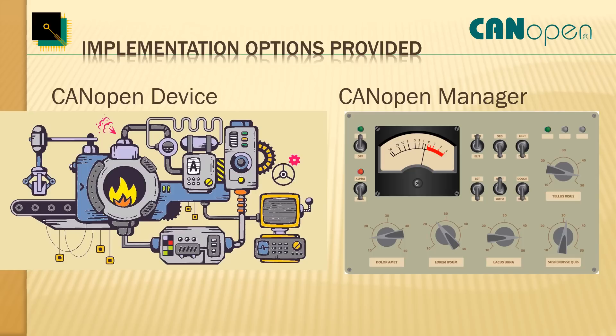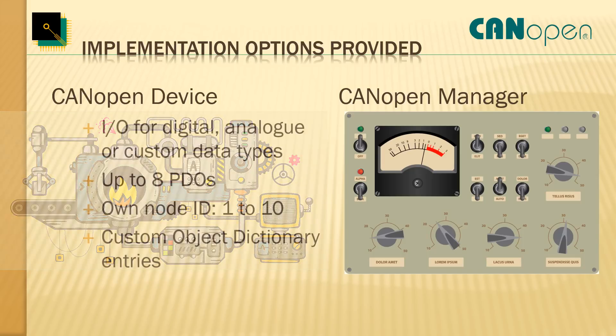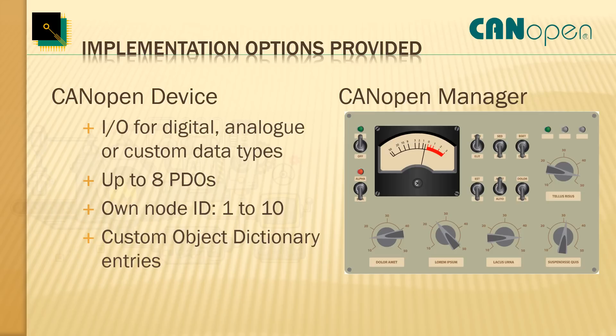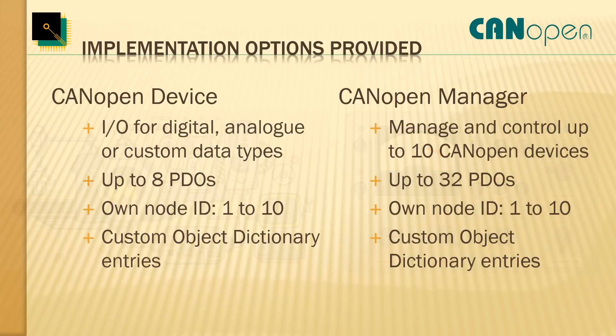Two library versions are provided. The CANopen Device Library is for simple I/O devices — sensors, actuators, digital inputs and outputs — with a limited number of PDOs, and the node ID must be in the range of 1 to 10. The second library is the CANopen Manager Library — the master controller — which controls up to 10 nodes on the system, communicates with sensors and actuators, detects their heartbeats, and can send operating state change messages and reset requests.